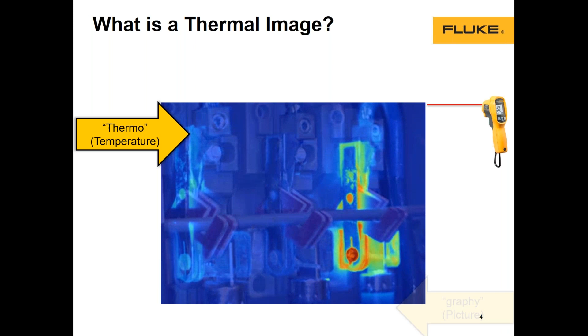And spikes in temperature, deltas or temperature signatures can tell us where we have issues that we can tackle later using either a power quality analyzer, a multimeter, or a VOM, or even a clamp meter. But always, the rule of thumb is that when we have a delta in temperature which is higher than the average temperature of the image, something's wrong, and it's an indicator that we might have a malfunction on the system. So, in summary, thermography is taking thermal data and visually displaying it as an image. Thermography.